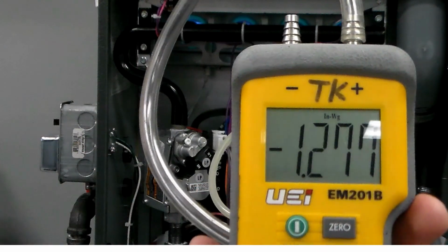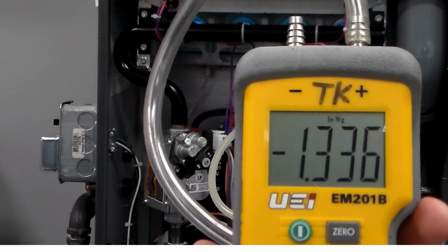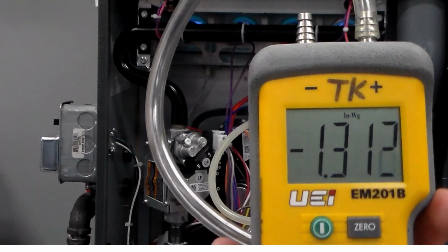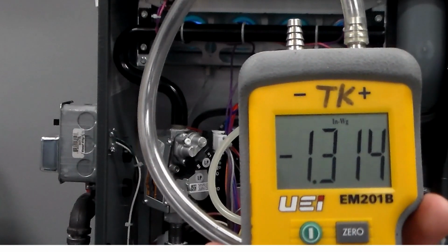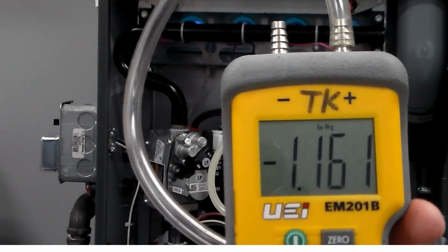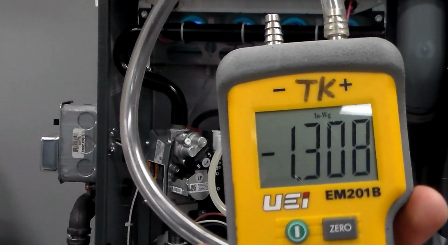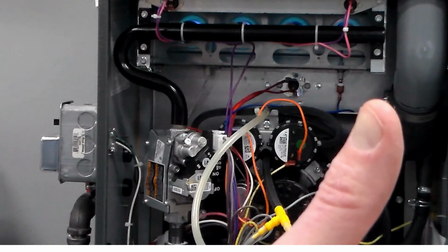And what can happen is that pressure switch can flutter fast enough that it will chatter the operation of the gas valve, and you'll lose flame and lock out on a flame rollout or loss of flame error before you will see an open pressure switch. So that can often be an issue. But again, all of that can be caught if you have a manometer teed into that, watching that draft the whole time. Like I say, this looks really good. I think we'll go ahead and pack up our instruments here and call this unit ready to go.